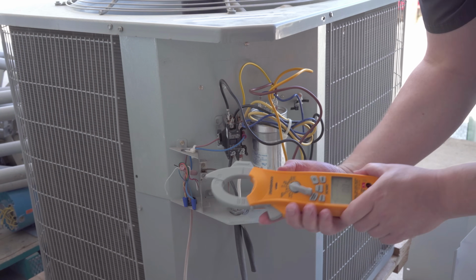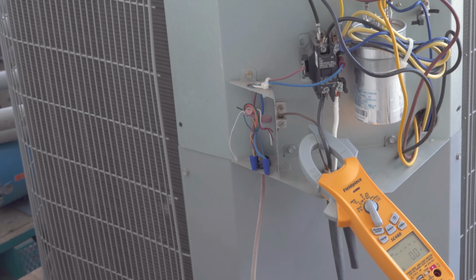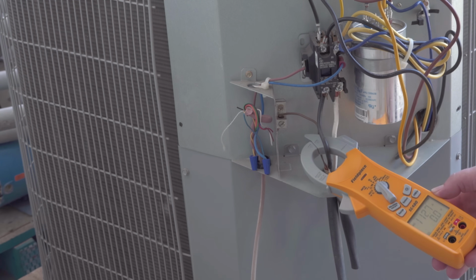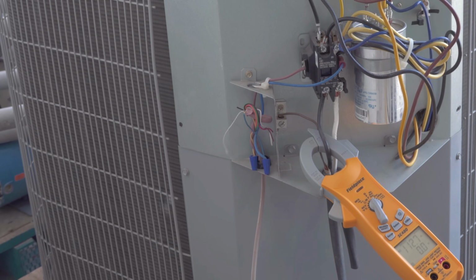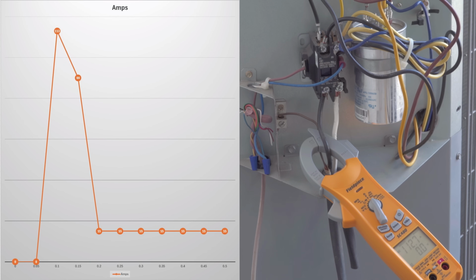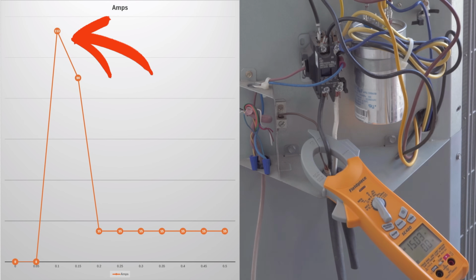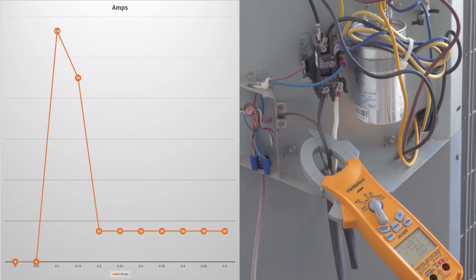Let's pop off the panel, hook up our multimeter tool, fire up the unit, and take a look at the inrush current. You can see that the inrush current was almost 113 amps, so we have 113 amps slamming into the unit in under a second. If you don't know much about electricity and you're asking, is that a lot? The answer is yes, that's a lot.